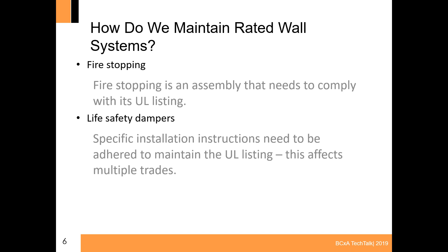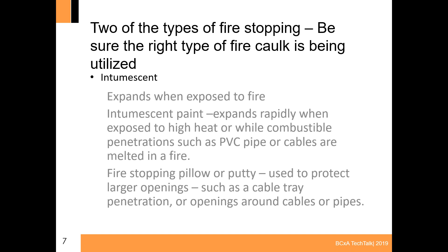The two types of fire stopping: we need to make sure we're using the right type of fire caulk for the right application. We have intumescent product, which expands when exposed to fire. It can be a paint, and it can also be pillows or putties, pre-made assemblies manufacturers make that can block the gap in case of fire, such as for cable tray penetrations, cables, and pipes.